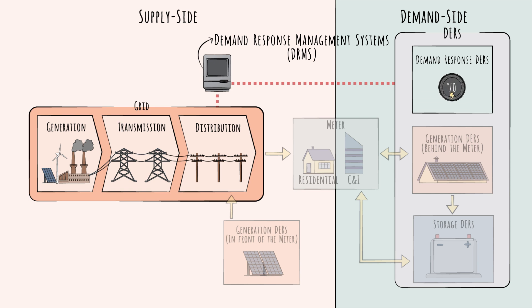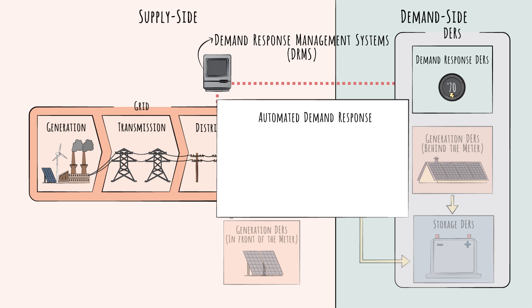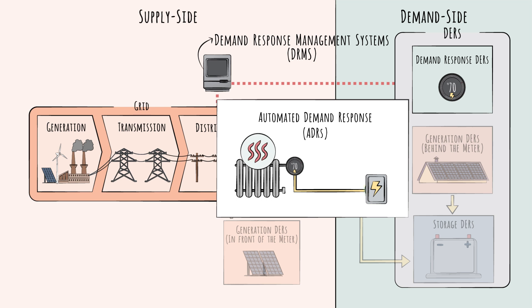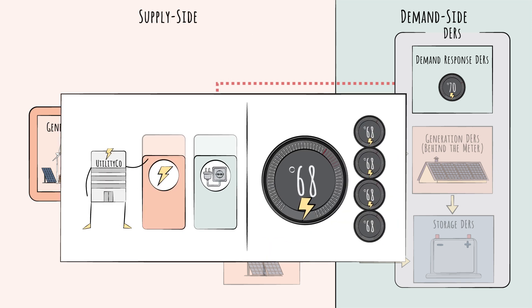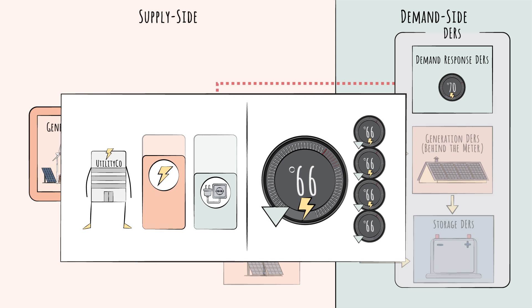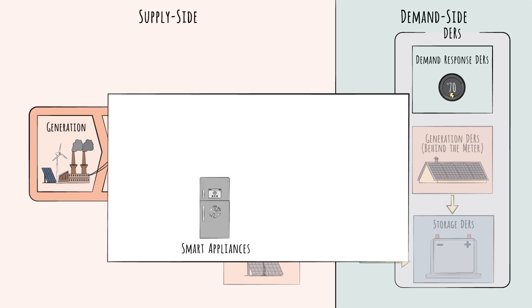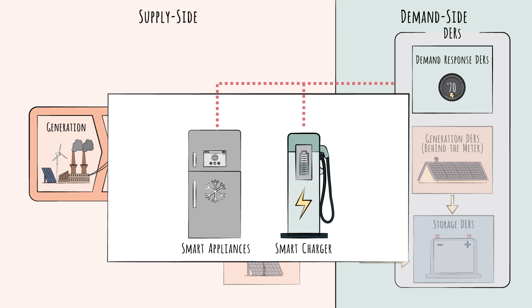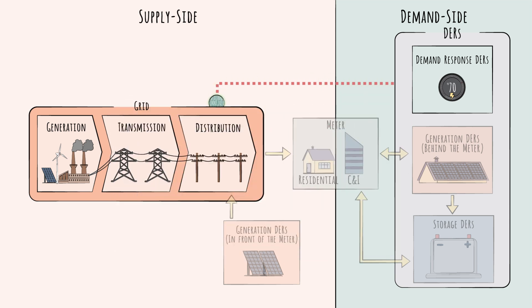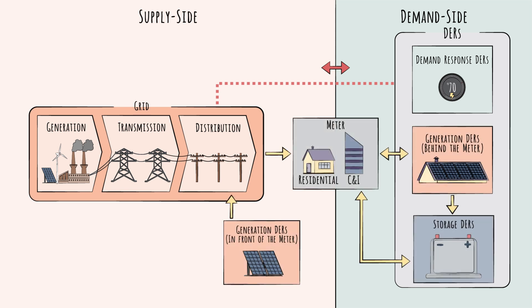In a more digitized, decentralized world, the vision is to trigger automated demand-response events, known as ADRs. The devices that can respond to an automated signal and find opportunities for demand reduction are the demand-response management DERs. A leading example is smart home devices like smart thermostats – by adjusting the set point temperature by a degree or two, a smart thermostat can reduce the site's power demand. Aggregated over thousands of sites, this creates a sizable grid impact. Smart appliances such as smart refrigerators and smart EV chargers also fall here, as they can increase or decrease their rate of charging based on demand-response events. Real-time responses from the demand side would require real-time information sharing to and from the supply side, and unlocking this will require significant changes – the focus of the next chapter.